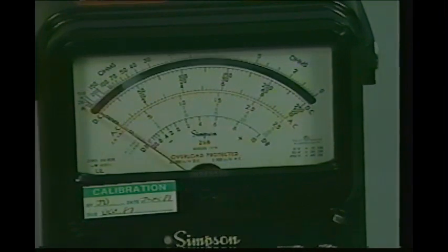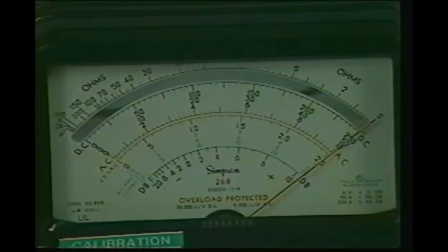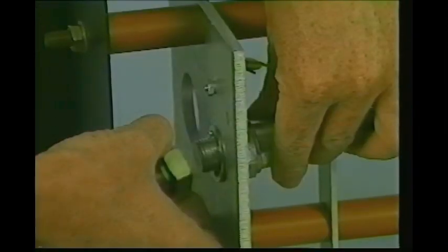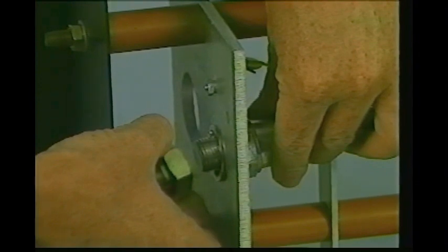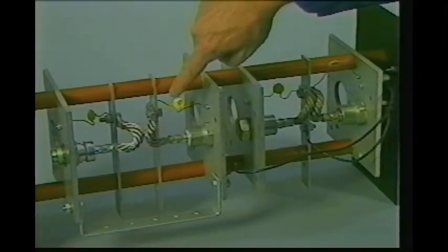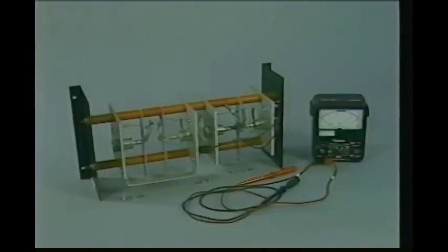A low reading and a high reading is an indication of a good diode. Two low readings indicated that the diode is shorted, and two high readings indicated that the diode is open. After determining which diode in the rectifier was defective, the diode was replaced. Then the capacitors and suppressors were examined to ensure that they were in good condition. The repair is completed.